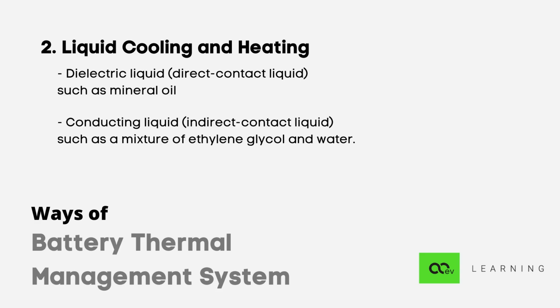For the direct contact liquid, the normal layout is a submerged module in mineral oil. For the indirect contact liquid, a possible layout can be either a jacket around battery modules, discrete tubing around each module, placing the battery modules on cooling or heating plates, or combining the battery modules with cooling or heating fins and plates. Between these two groups, indirect contact systems are preferred in order to achieve better isolation between battery modules and surroundings and thus provide better safety performance.